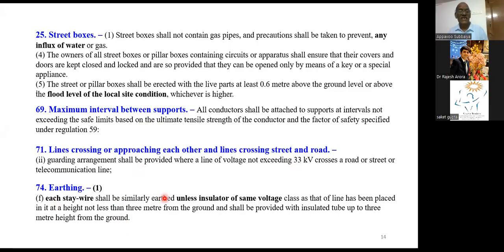Another thing, the stay wire. I have seen one accident where a lady in an agricultural area came into contact with the stay wire and got electrocuted. There should be an insulator of the same voltage. Say if you have an 11 kV pole, then it should be of 11 kV. Are you having these 11 kV guy insulators? This is called colloquially a guy insulator. It is fixed in the stay wire and separates the length from the pole up to the insulator and from the ground up to the insulator, so that a person who comes into contact with it doesn't get any injury due to electrical leakages.